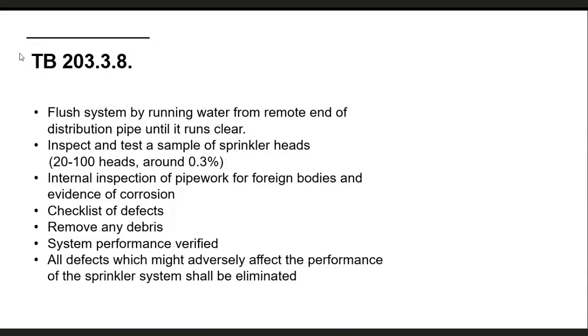There's a checklist of defects you need to work through - for example, looking at what you've actually taken out of the sprinkler system. Are these bodies greater than 5 millimeters? Are they discharged in routine water tests? Are there foreign materials? Is there evidence of microbial activity? Is there evidence of persistent pinhole leaks or nuisance activations of alarm valves? There's quite a list of these things, and depending on how many you tick would depend on the remedial actions required.